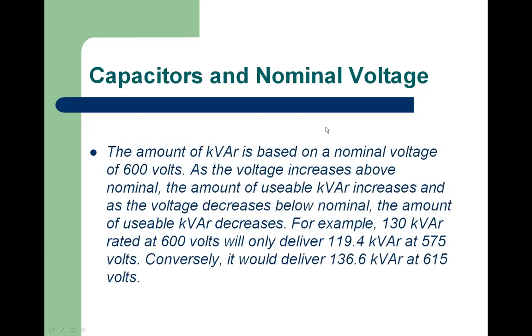Now, one of the things that we need to think about is the amount of kVAR. If you have capacitors put in and they say you need 100 kVAR, and then you notice on your power factor, on your hydro bill, you're supposed to be at 90 and you're only hitting 88.9 or 89.1, it could have to do with the voltages in your facility.